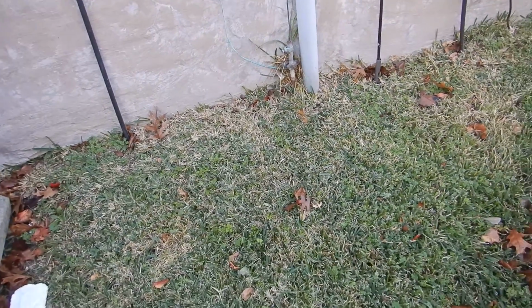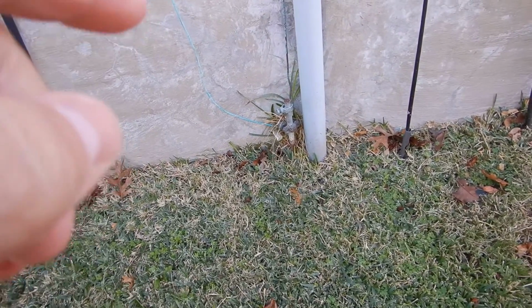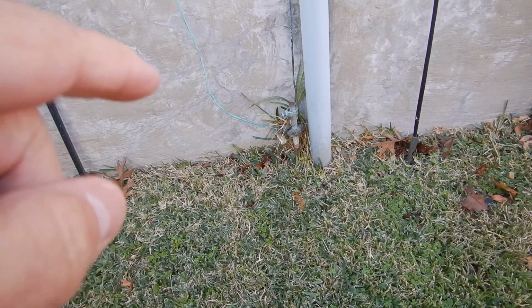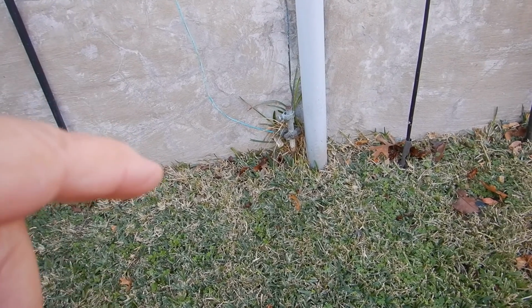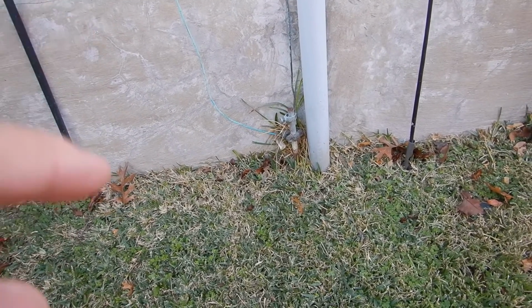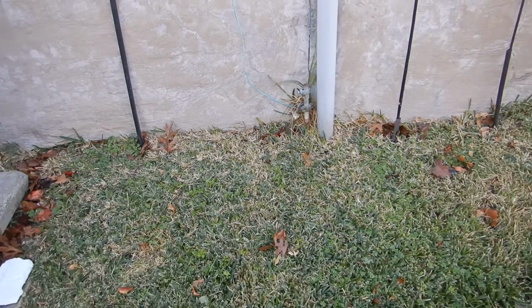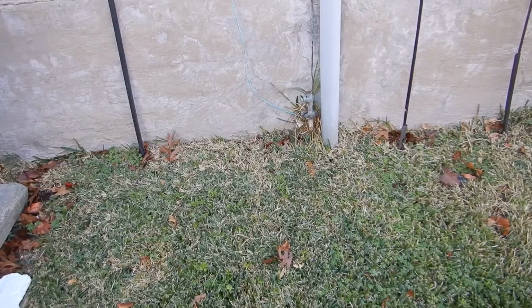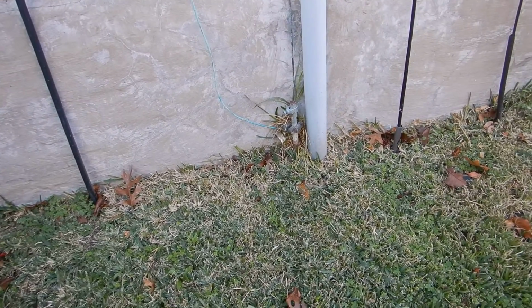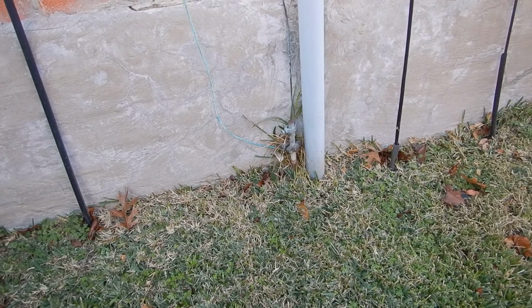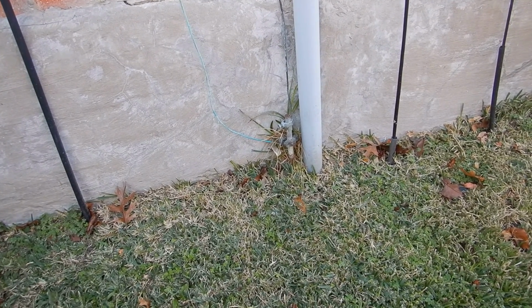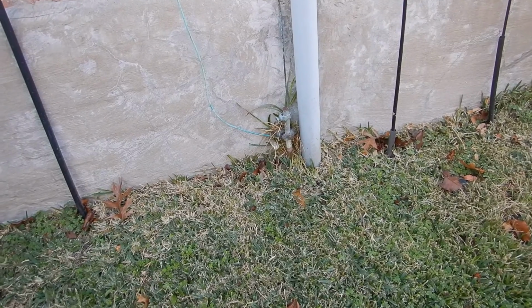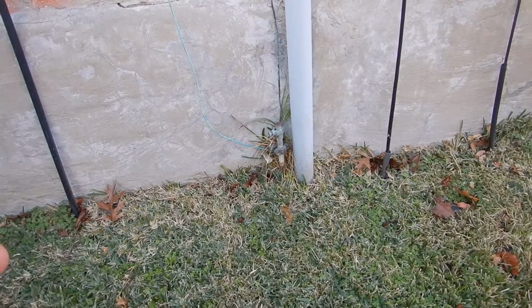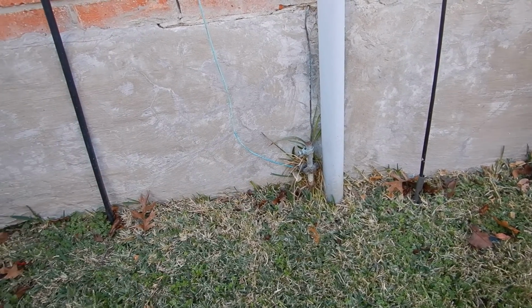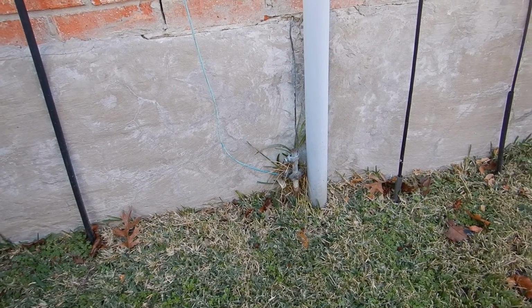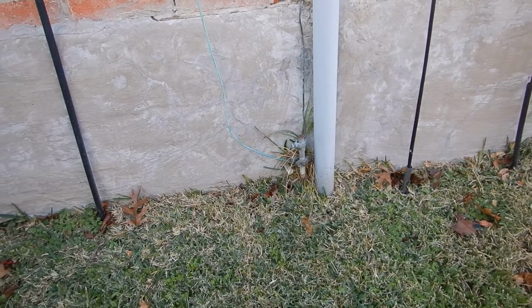I have no idea. But I do know that this supposedly 8-foot rod is supposed to be buried 8 feet. It's not supposed to be buried 7 feet and 3 inches, 7 feet and 6 inches. It's supposed to be buried 8 feet. Now an electrician might be able to measure the resistance on that and prove to the code inspector that there's enough resistance so that it meets the intent. I mean, that's what happened at my house, but I was there when mine was installed. I was not here when this was installed. I have no way to know whether this grounding rod meets the proper resistance or not. I do know that according to code, this grounding rod was not sufficiently buried.